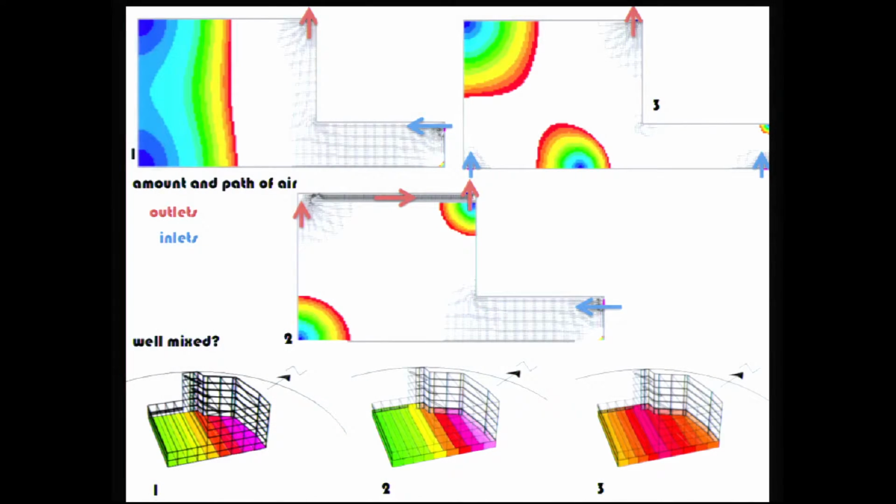We're looking at a lobby space of a large institutional building, and we had 3 design alternatives. Again, iterative approaches, right? These graphics on the bottom are the distribution of CO2 based upon night flush and daytime fresh air ventilation approaches. And what you see in the image in the bottom left corner is a lot of diversity across that floor plate from a CO2 parts per million representation. And that was our first design strategy, our second, and our third.